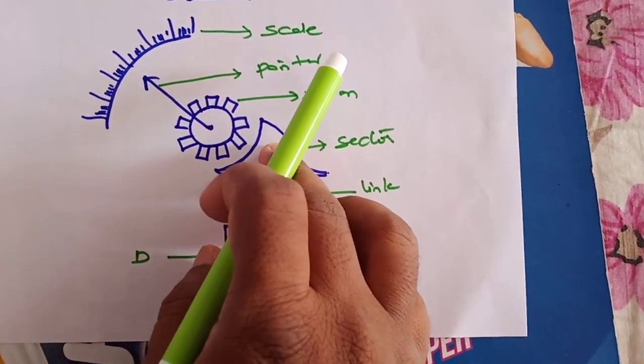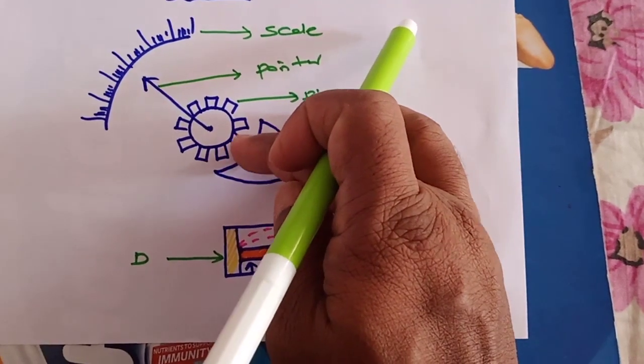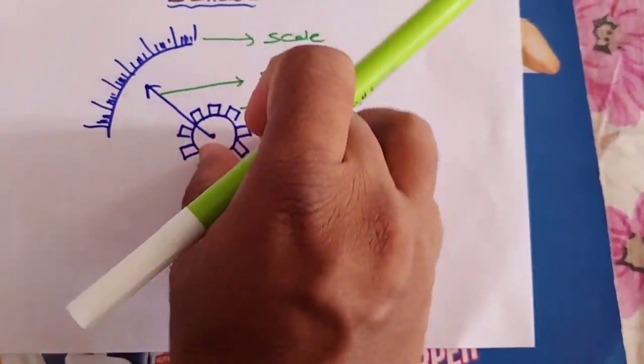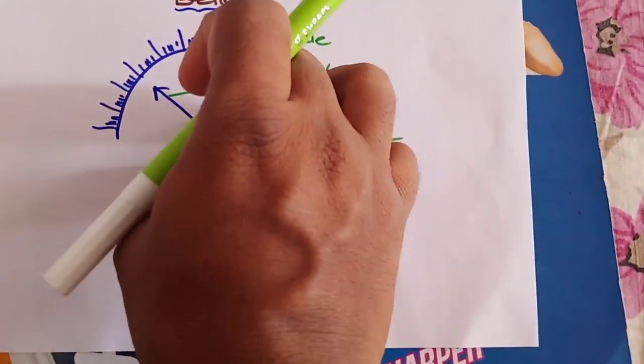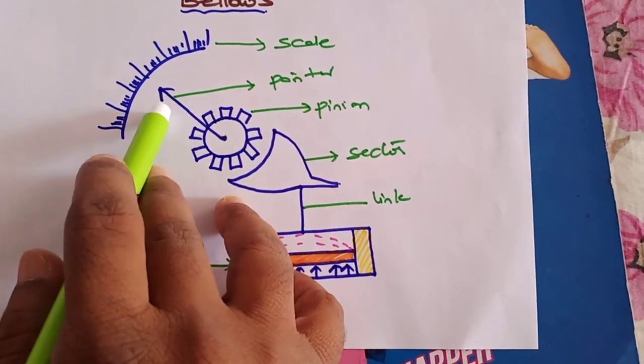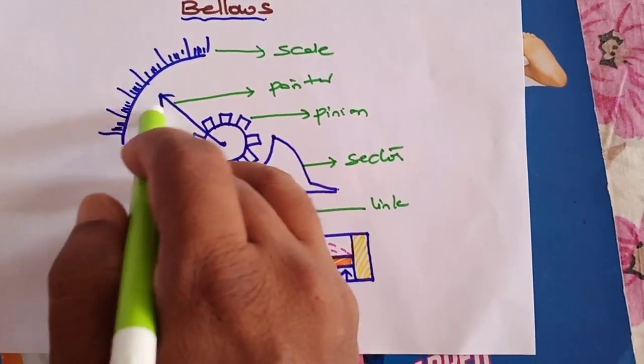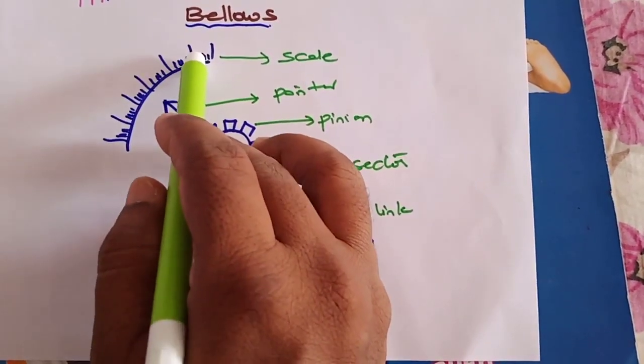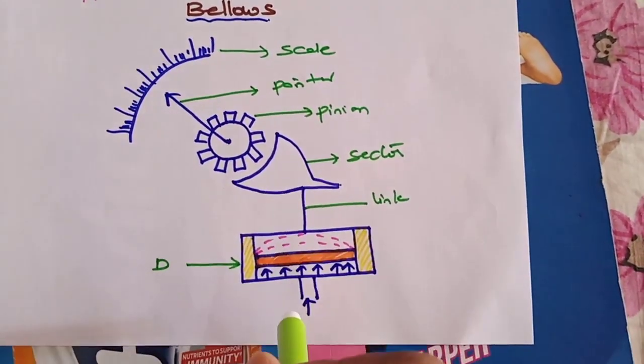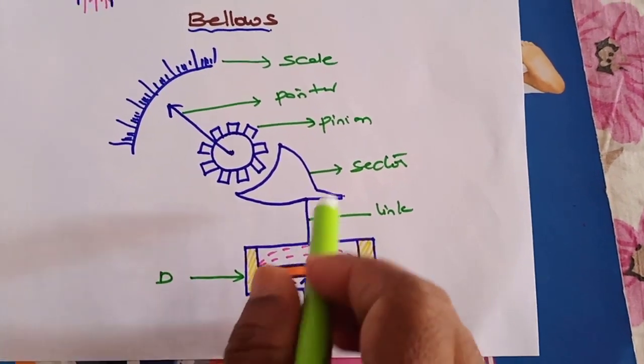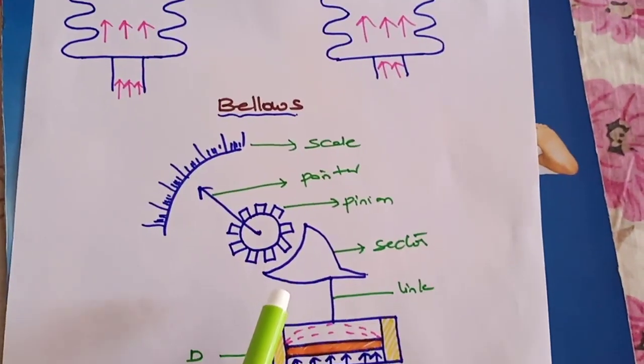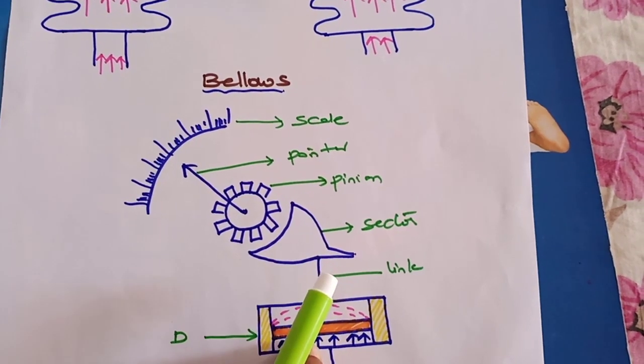As it expands, the link connected to the sector, which has a teeth-like structure, slightly moves the pinion. As the pinion moves, the pointer connected to it starts deflecting, showing a reading on the calibration scale that indicates the value of pressure or force being measured. This is about the diaphragm type of measurement of pressure or force.